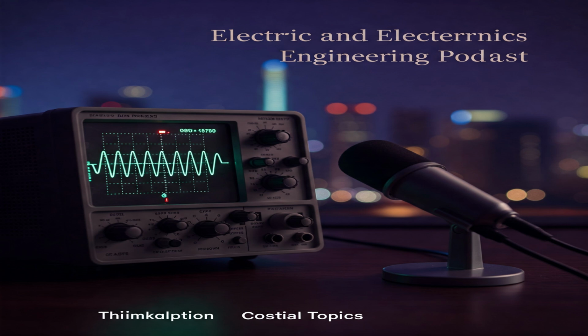Excitation systems. Yeah, that's crucial. Older systems used a separate smaller DC generator called an exciter, often mounted on the same shaft. Its DC output was fed to the main rotor field via slip rings and brushes. Prone to wear and tear, I imagine. They require maintenance, yeah. So modern systems often use static excitation or brushless excitation. Static systems use rectifiers to get DC power from the alternator's own output or an auxiliary source. And brushless. Brushless exciters are clever. They have a small AC generator, the exciter, on the same shaft, but its armature is on the rotor and its field is stationary. The AC output from the exciter armature is rectified by diodes, also mounted on the rotating shaft, and this DC current is fed directly into the main alternator field winding on the same rotor.